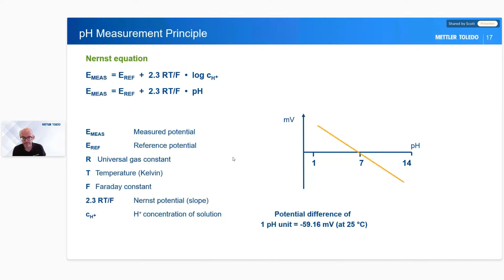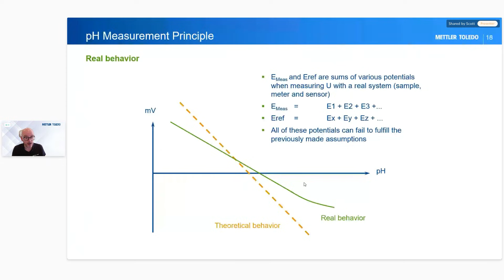So the next problem is we all work in the lab, and we all know that in real life, nothing ever happens as it's meant to in theoretical behavior. So when we're actually taking a measurement, we've got the whole system: the electrode, the wire in between, the buffers to do calibration, all sorts of different things going on. In actual fact, this is the theoretical behavior as we think it should be, and then we get something that's called the real behavior. And the next bit of the slides is how we can compensate for that real behavior, and that is through calibration and adjustment.